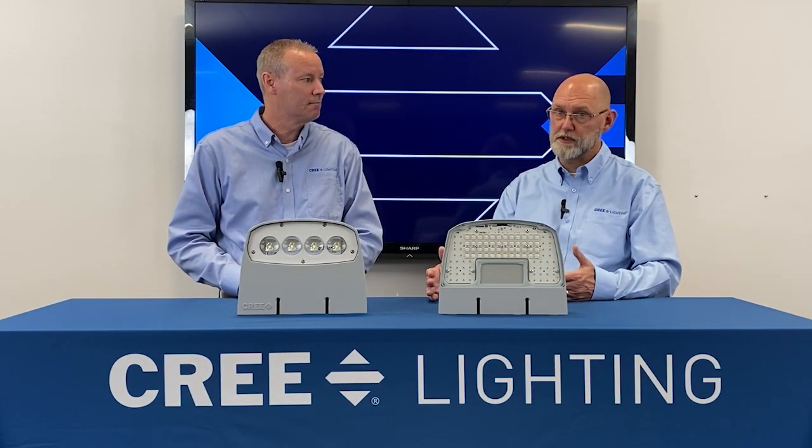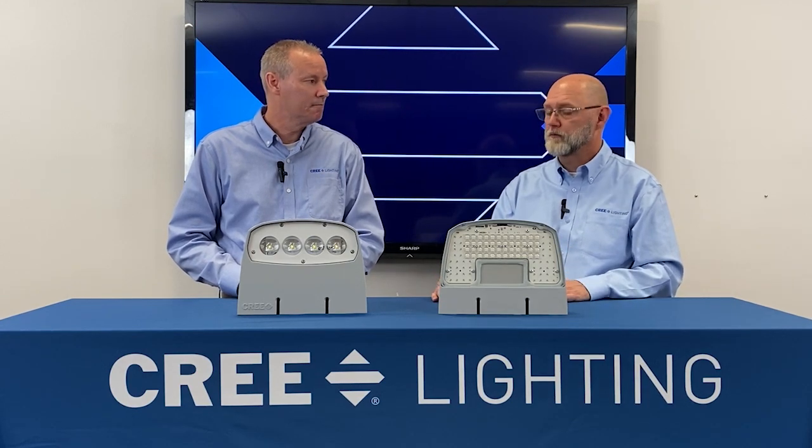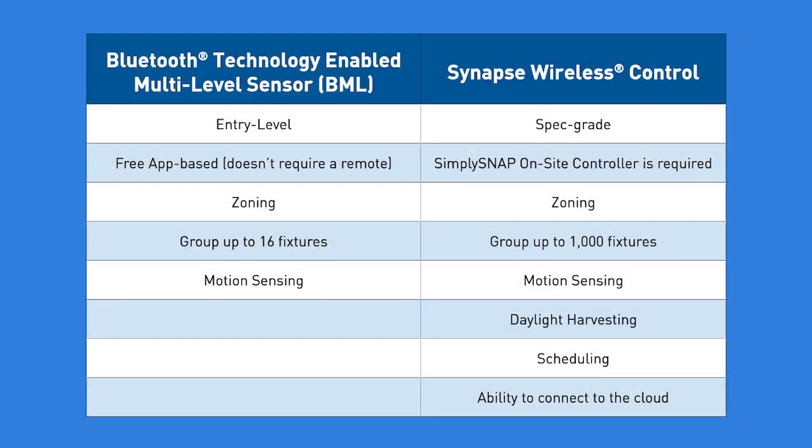Let's talk about controls. I see we still have the ML option — the multi-level option — on our spec sheet, but the programmable multi-level option has been removed and replaced by what? The PML is going away and being replaced with the BML, which is a Bluetooth multi-level. One of the biggest benefits is that while you still get the same range and coverage as the earlier version, you can now control it with an app on your phone and no longer have to purchase a secondary controller. And can I do grouping with those? Yes — with the BML you're able to control up to 16 fixtures. We also still have the Synapse zero-to-ten interface, so if somebody wants to pull a wall mount unit into their Synapse lighting controls system, that's possible as well — just another feature to help better manage your energy usage at your site.